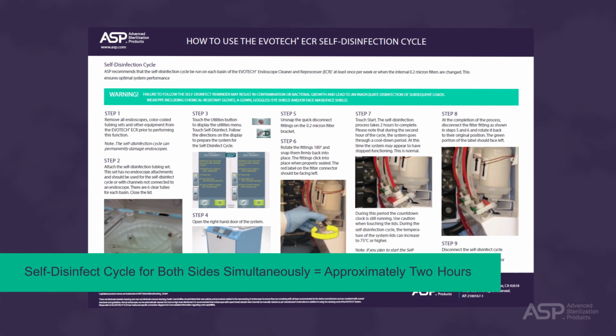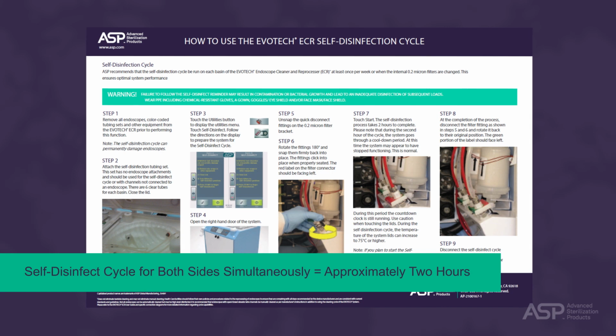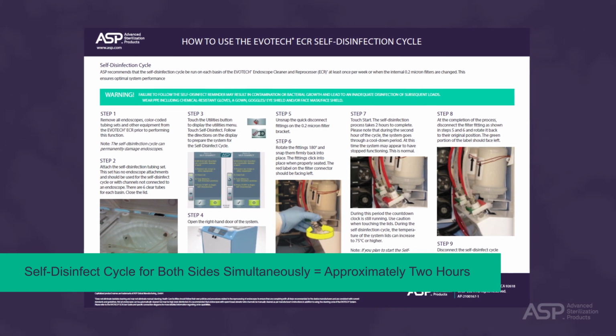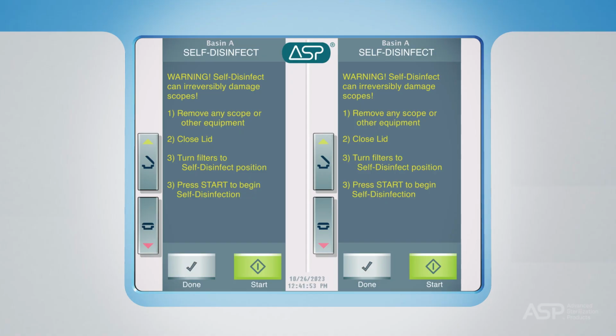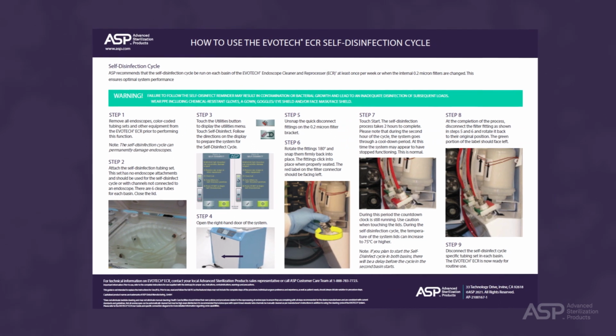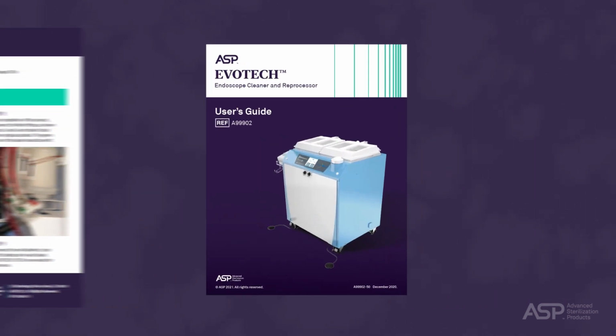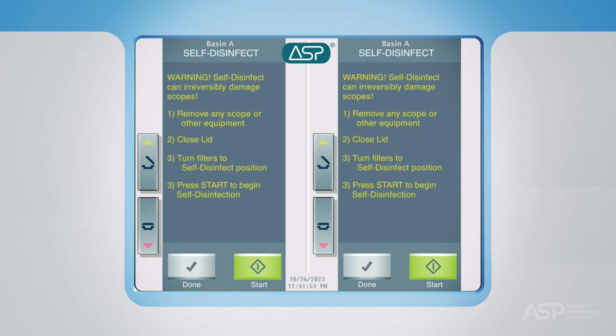The length of time to run a self-disinfect in both sides simultaneously is approximately 2 hours. The EVOTECH ECR will display a pop-up reminder when it is time to self-disinfect the system. Follow the step-by-step instructions in the self-disinfect wall chart or the user's guide. Failure to follow the self-disinfect reminders may result in contamination or bacterial growth and lead to an inadequate disinfection of subsequent loads. PPE is required for this process, and both basins must be empty to run a self-disinfect.